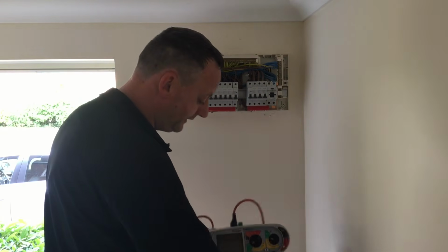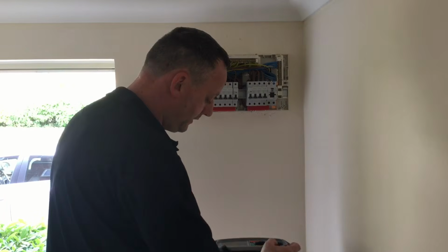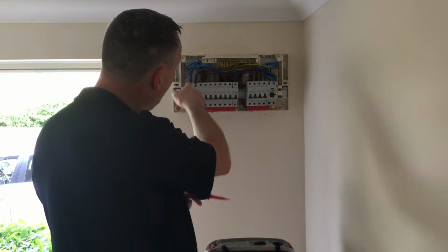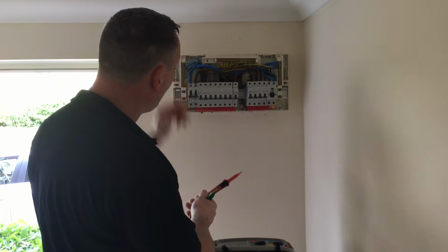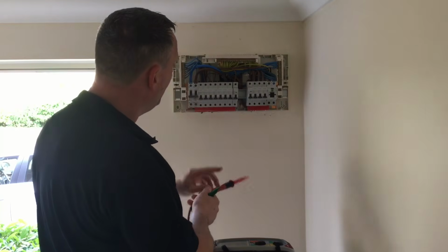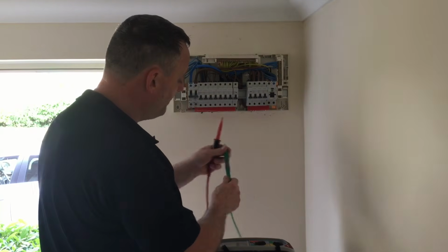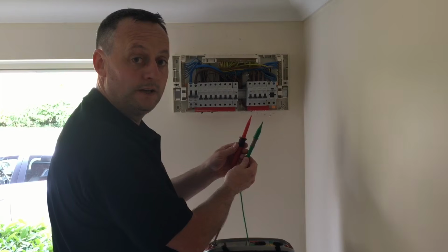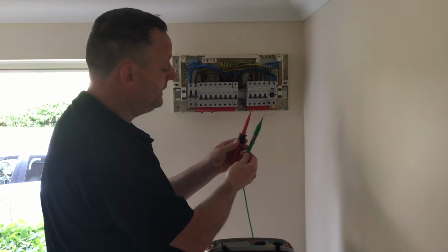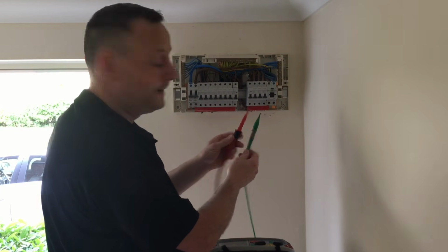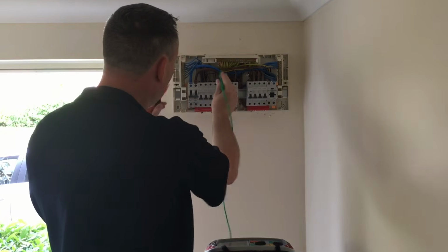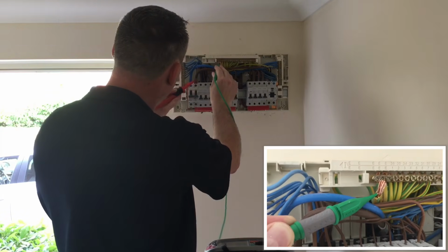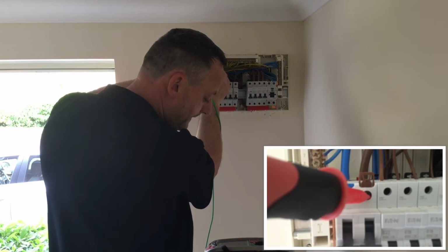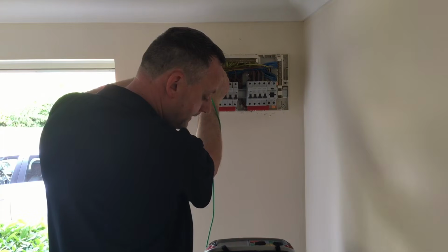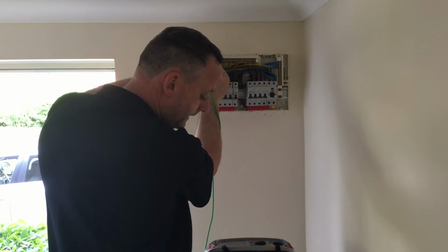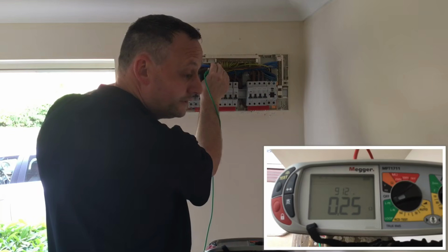I'm going to probe onto the least dangerous conductor first, which in this case is the earthing conductor, and then onto the line to do the test. And when I come back off, I'll pull off the line conductor first and then off the earthing conductor second. My probes themselves conform to GS38 with no greater than 4mm exposure tip. This is considerably less than 4. So I'm going to probe onto the earthing conductor first, and then I'm going to probe onto the line conductor. And I've got a reading of 0.25 of an ohm.